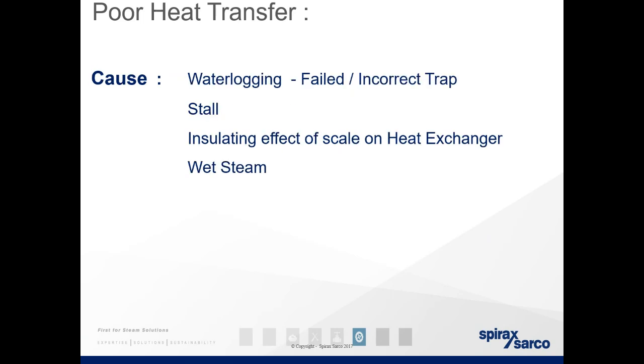So the causes: it can be waterlogging, so added water in your system from failed or incorrect traps. Scale can also cause that problem, the insulating effect of scale. If you have a buildup of scale or particulates in your pipe, that's acting as a barrier to heat transfer into your process. And wet steam as well, so it's no longer the temperature you require. The water doesn't give up its enthalpy as easily as the steam does, so you have less heat transfer.